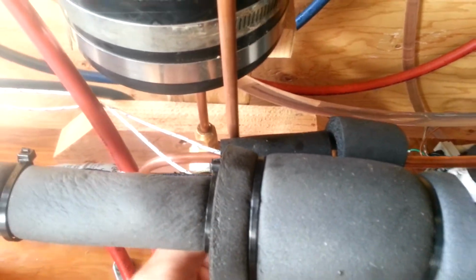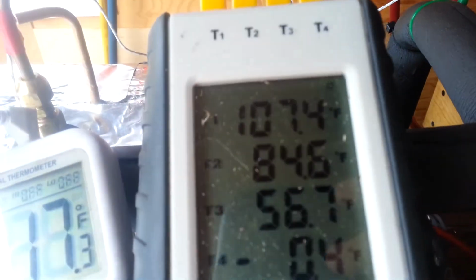Now this temperature here on the top, 107.2, that's taken from a thermocouple directly on the surface, almost directly on the surface. There's some electrically insulating tape between it and the copper tubing coming out of the compressor. A little bit of insulation around it to get a little better reading. But I think it is interesting that that value so closely corresponds to the condensing temperature at that pressure.